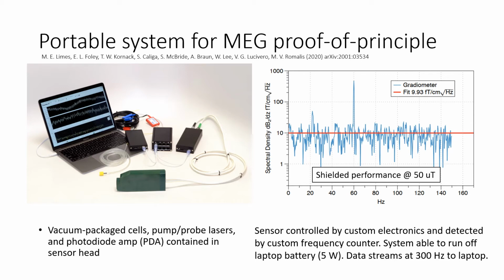This black box really replaces a rack of test equipment I would typically need to run this thing. So throwing the sensor into a Twinleaf MS2 magnetic shielding, I get about 10 femtotesla per centimeter per root hertz at half a Gauss. This thing works pretty well. There's a loss in sensitivity from optimal, and we're still trying to figure out why. But this is good, but it's still shielded. We want to be unshielded.